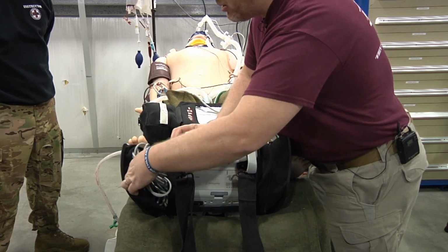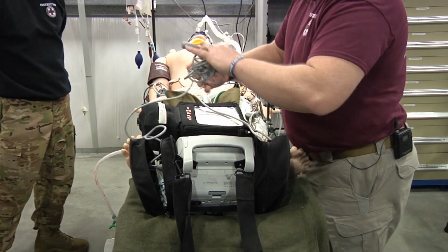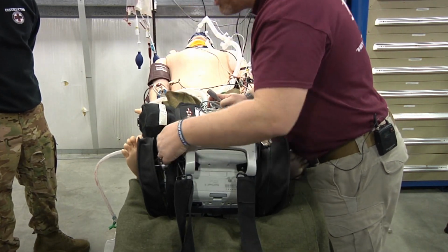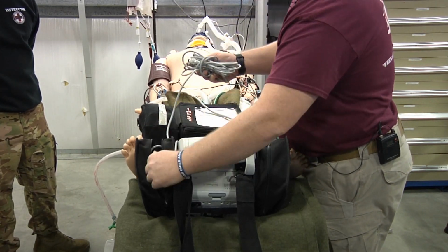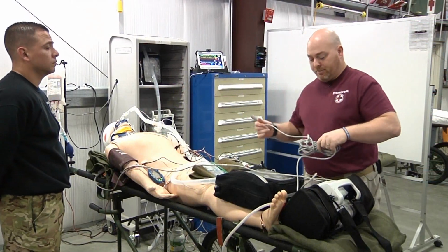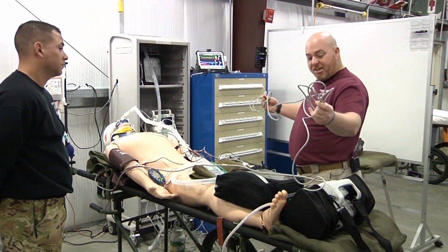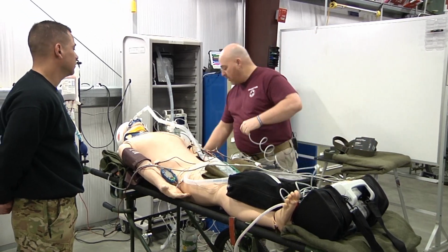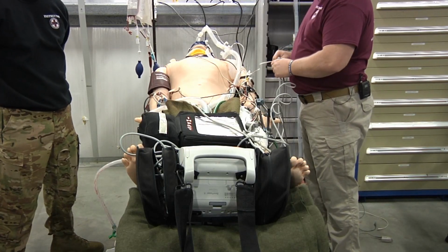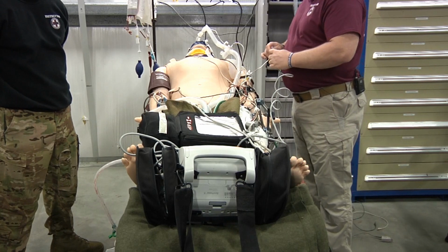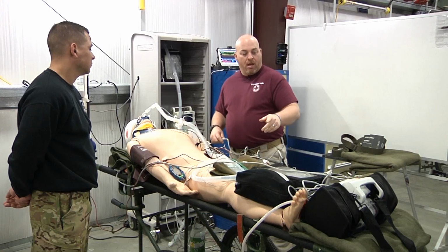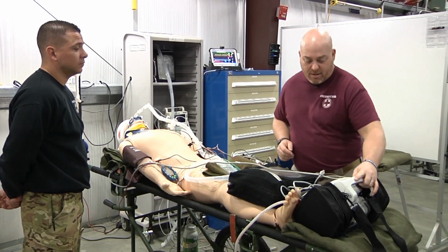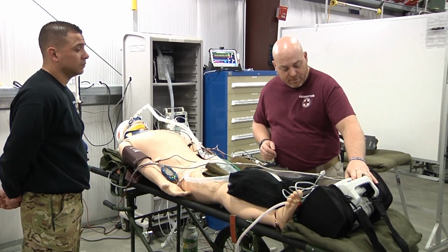Now we also have to zero our invasive line. So I'm going to pull out my pressure cable. I'm going to ensure that I'm in whatever pressure I'm in. I'm in P1. All right, look at all this excess cable. So we're going to put as much back in the bag as possible when we can. We're going to take them off their A-line monitoring. As soon as I plug them in, my monitor is going to identify that I've hooked up to a pressure line.